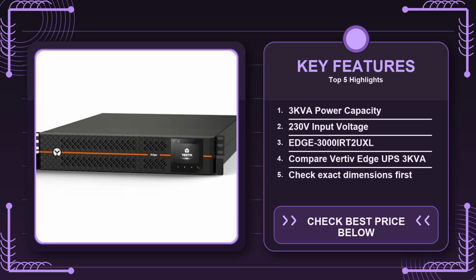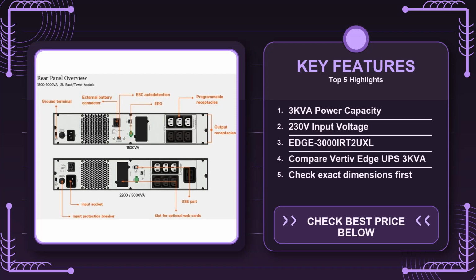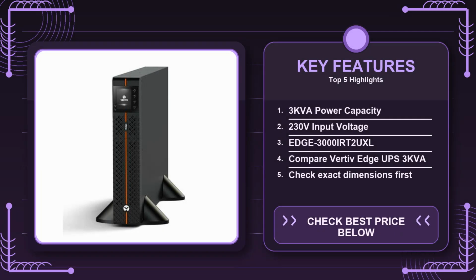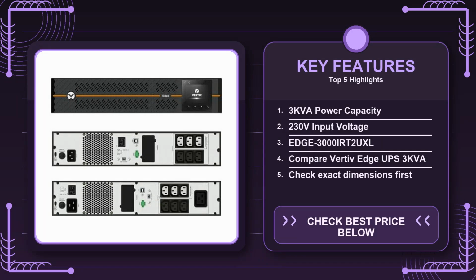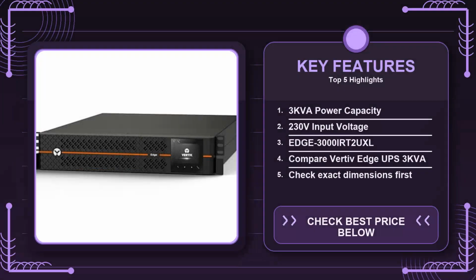Let's break down the practical strengths. First, the battery runtime is decent for its size. With a standard lead-acid battery pack, you can expect around 8 minutes of backup at half load and about 2 to 3 minutes at full load. That's enough time to either keep a server running long enough for a graceful shutdown or to give you the window to switch to a generator.